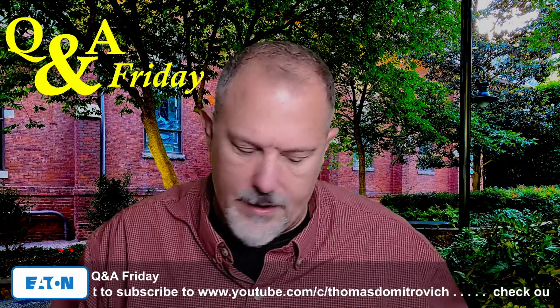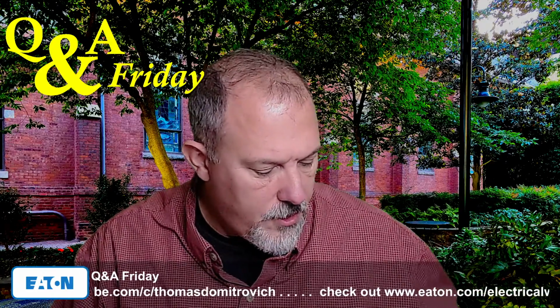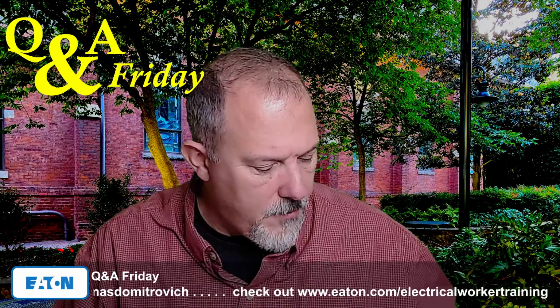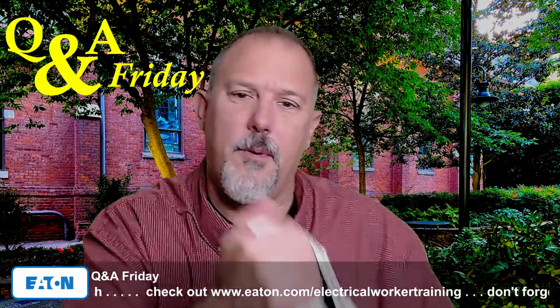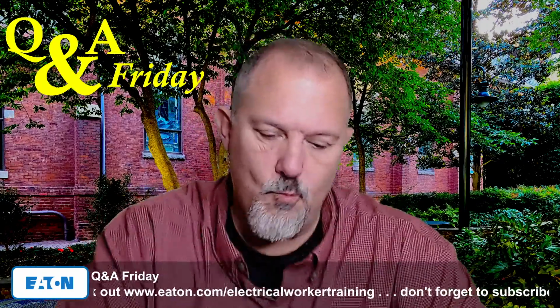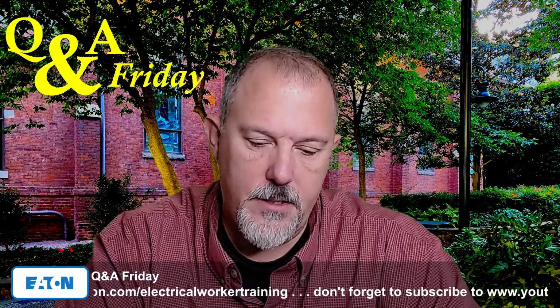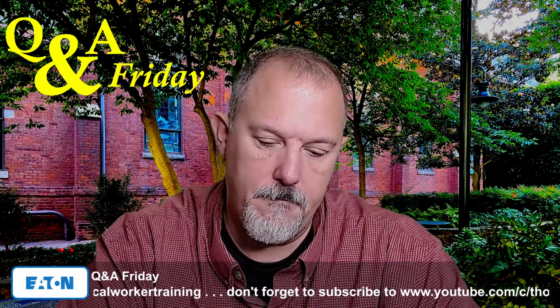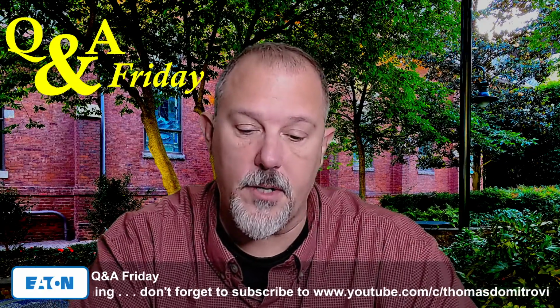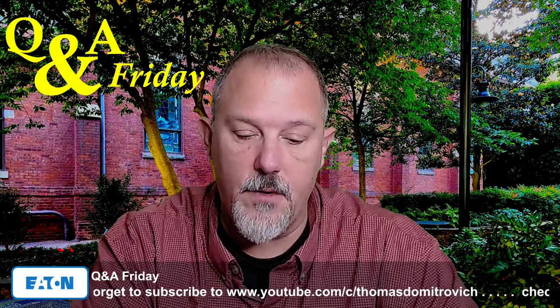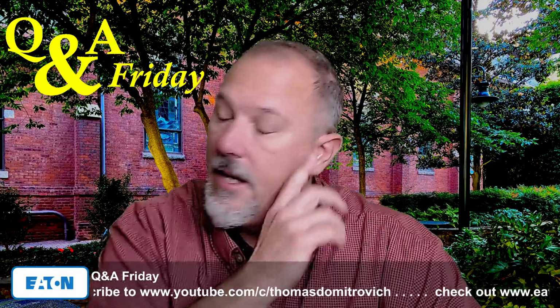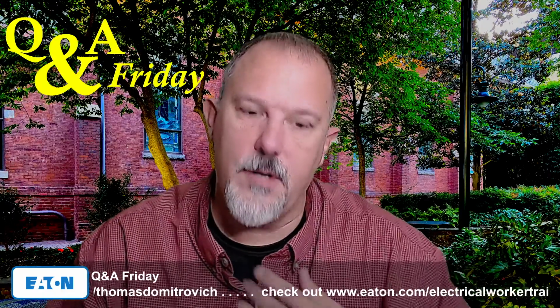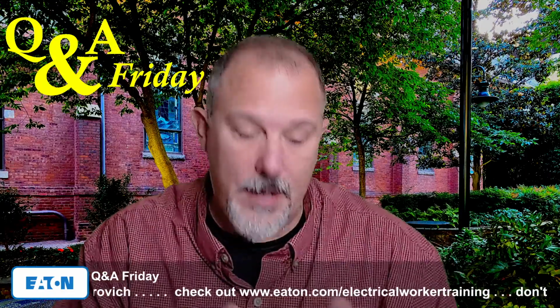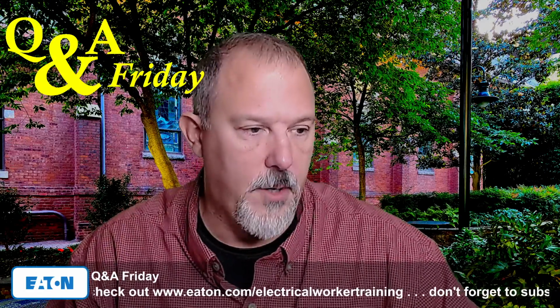Let's go back to 240 again, because it says where a circuit breaker is used on a circuit having available fault current higher than the marked interrupting rating. A good point, Robert. So when we say series ratings, we're specifically talking about a circuit breaker. The other areas, when we talk about using up, over, and down, it's not a series rating, because series rating is only for circuit breakers.